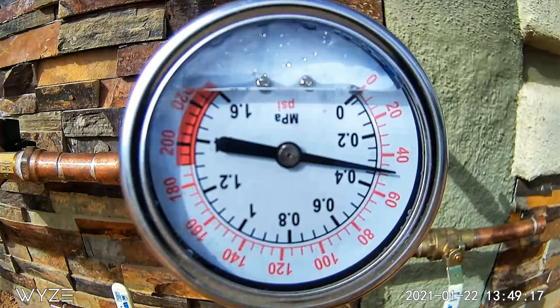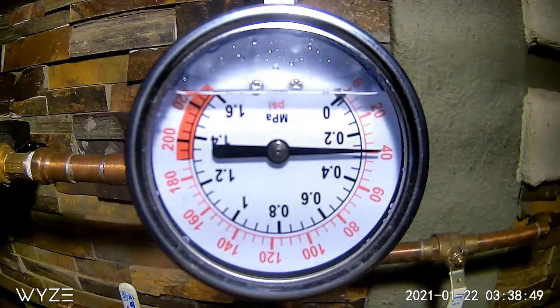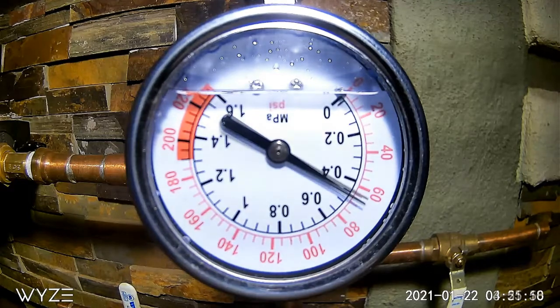In the one-hour test, it looks like about 2 psi is lost. But when the water heater turns on to maintain temperature, you can see there is a spike of 25 to 30 psi over the course of five minutes. As soon as the water heater stops heating, the water immediately starts cooling and begins shrinking. The water is always in flux, either expanding or contracting, creating constant movement of water inside your plumbing.